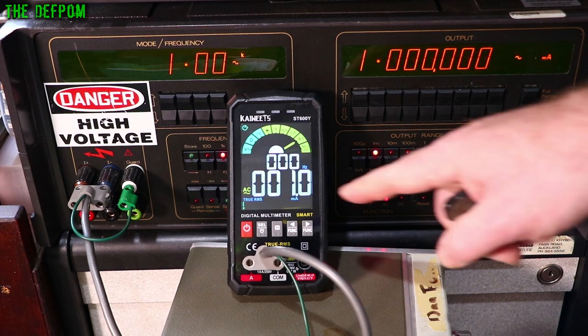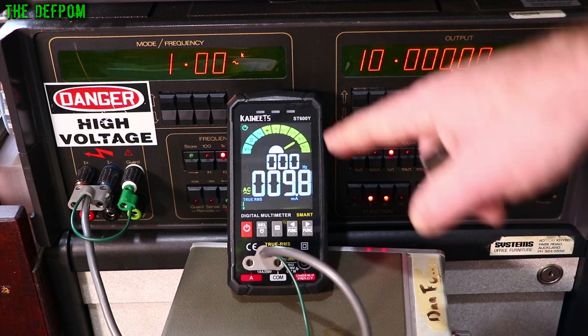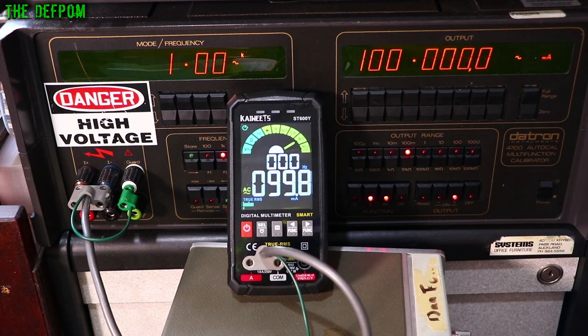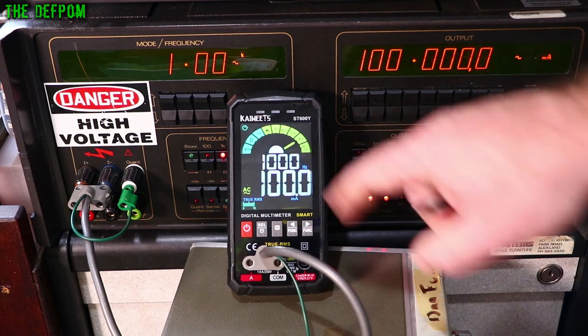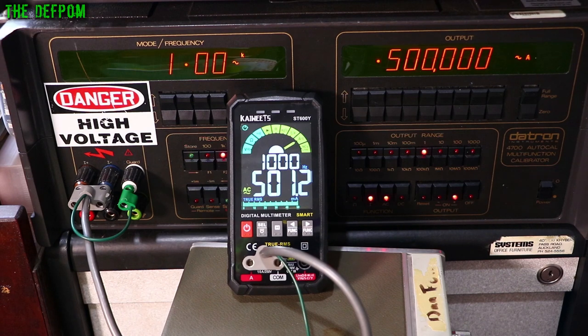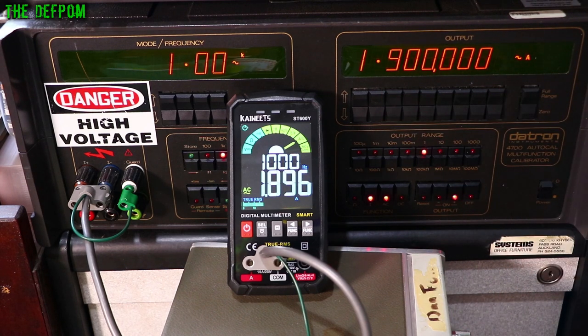Now doing 1mA AC: it's showing it but can't measure the frequency — probably not getting enough voltage for that. At 10mA: still can't measure frequency, and it's two counts out. At 100mA: two counts out but still can't measure the frequency. At 500mA towards the top of the lower range: 12 counts out, still can't measure frequency. At 1A AC: one count out — pretty good. At 1.9A: reading slightly high but pretty close. It's all within spec.